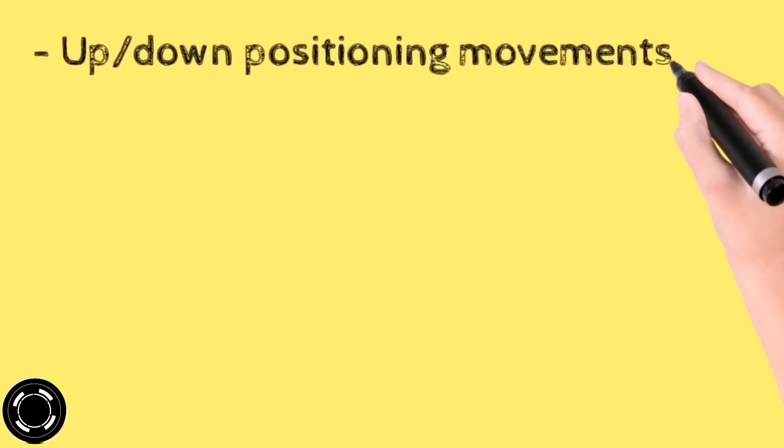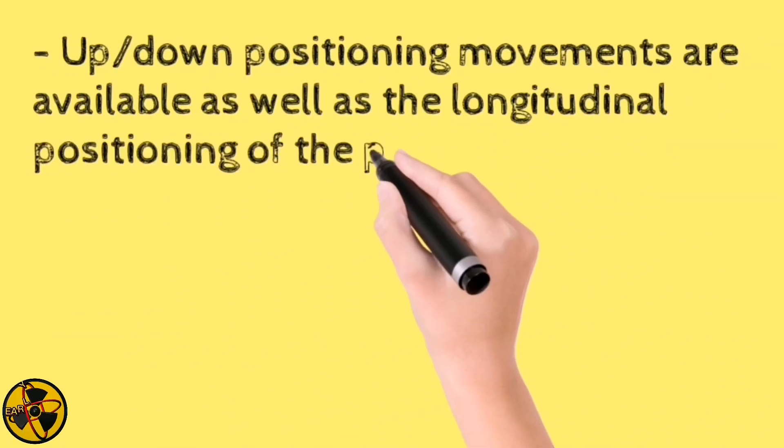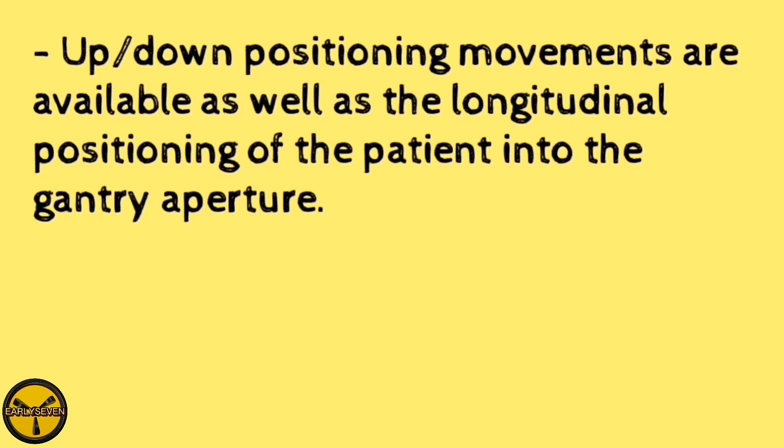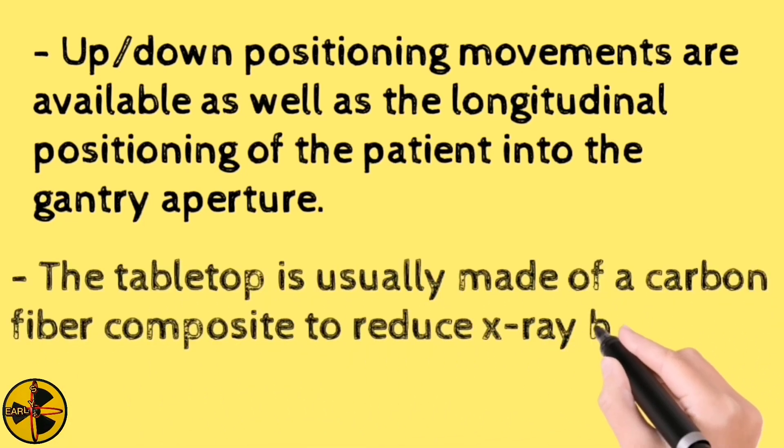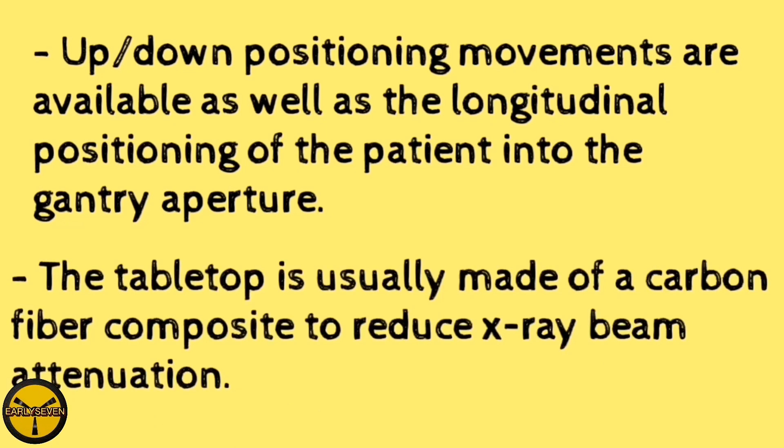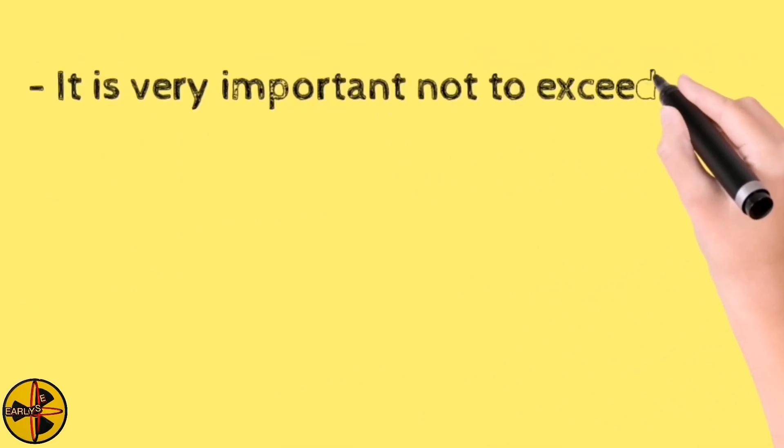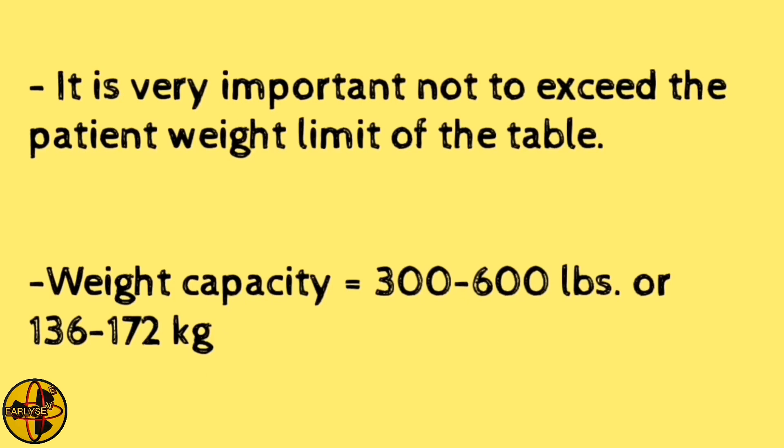Up and down positioning movements are available, as well as the longitudinal positioning of the patient into the gantry aperture. The tabletop is usually made of a carbon fiber composite to reduce x-ray beam attenuation. It is very important not to exceed the patient weight limit of the table. The weight capacity is 300 to 600 pounds or 136 to 272 kilograms.